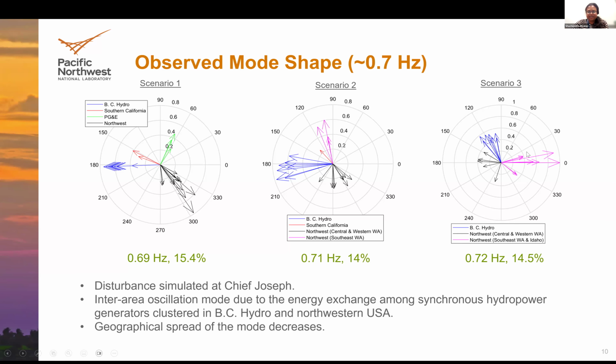As we keep increasing the inverter penetration, because the hydro generators in the Northwestern cluster are not changing, initially with that drastic change of replacing all the coal generators, the frequency of the north-south B mode - which doesn't exist anymore as a system-wide mode - increases quite a bit, to 0.69 hertz. With further changes the frequency shows a slight increasing trend, so now we have a mode around 0.7 hertz, and what we observe is the generators in British Columbia are swinging against those in the US Northwest.